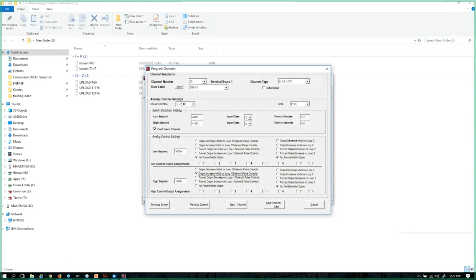So we can do the same thing with output or with loop 2, and we have high and low control set points. Now, one such place that you might see this really common on some of the panels that I design or have been involved with the design on would be SO1. And let's see, what would I do? What's very common on a low control set point?